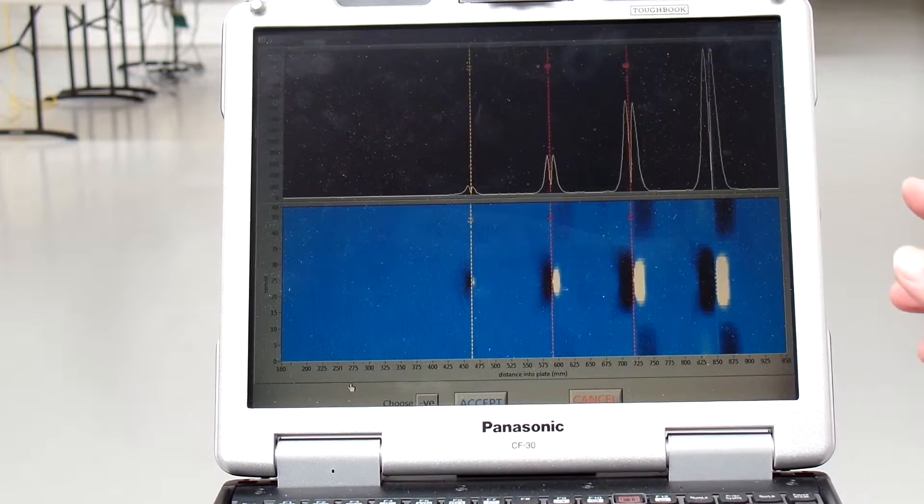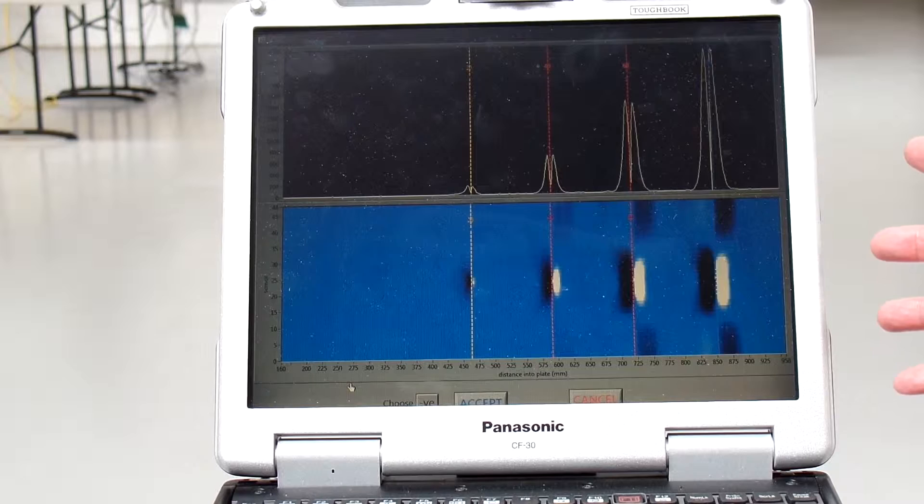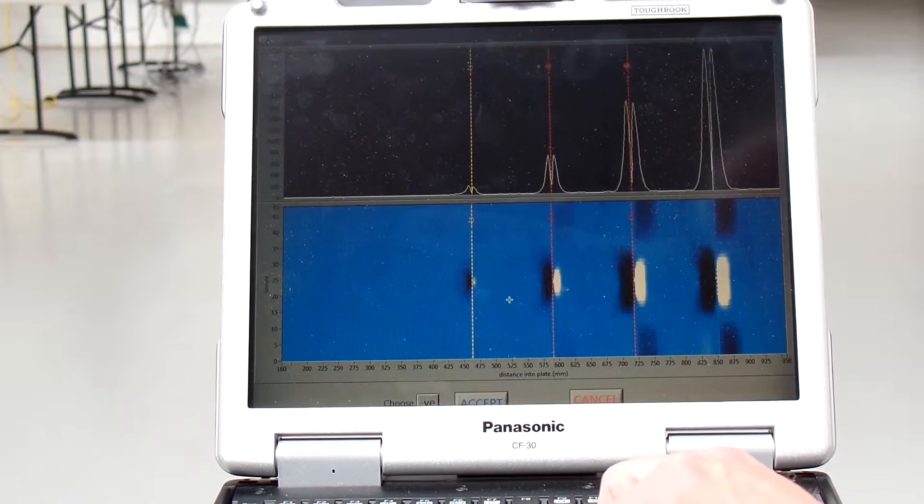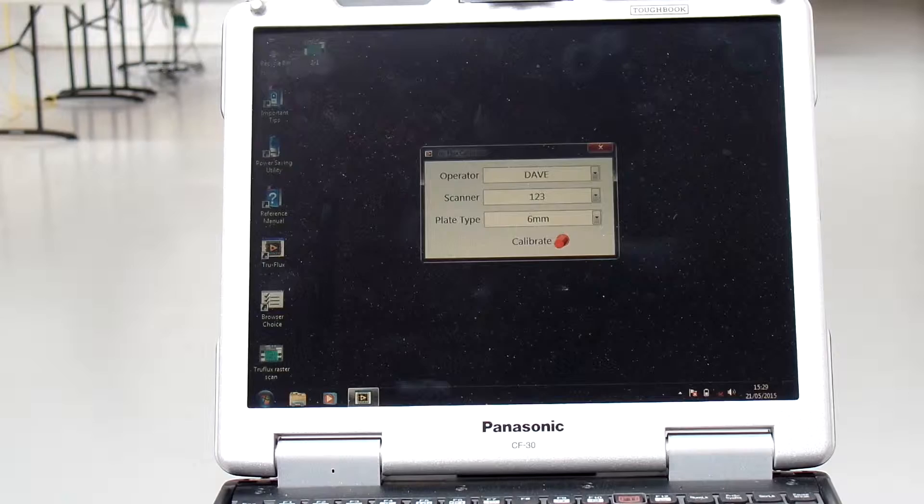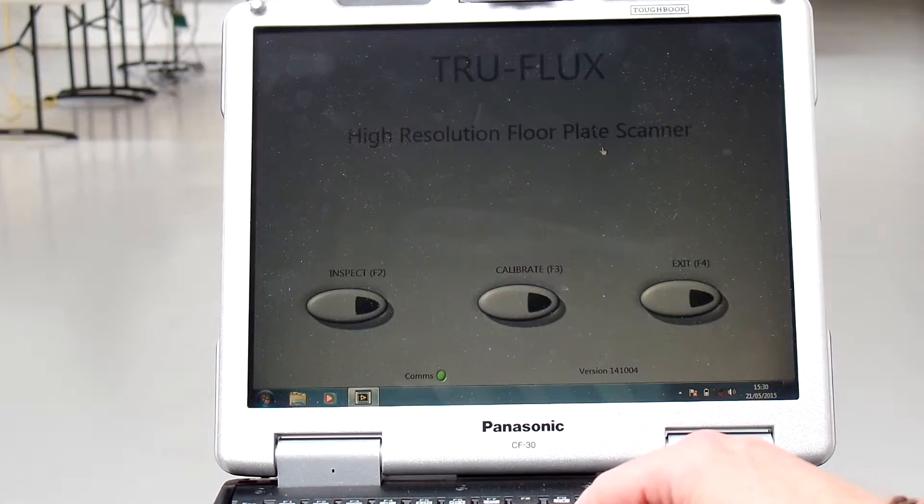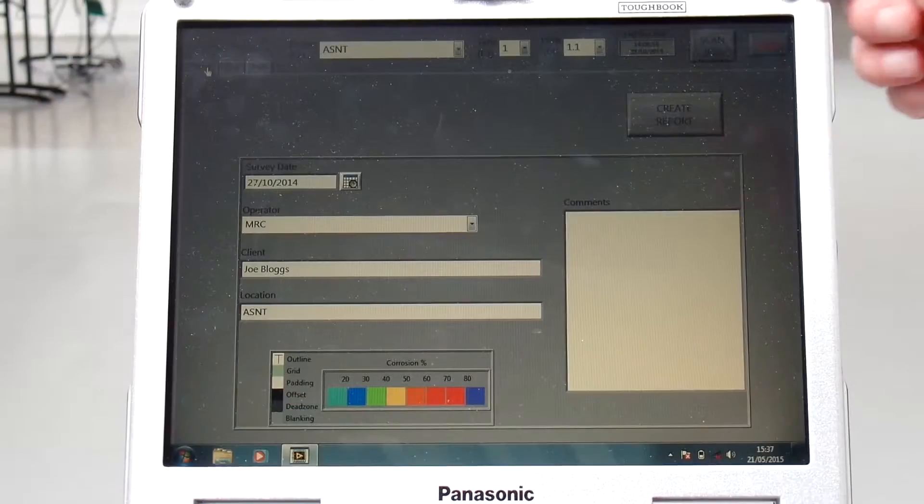With the cursors in place on the indications, we press the accept button to accept the calibration. You must perform a calibration before an inspection. The calibration will be stored for a period of up to 30 days, after which point a calibration must be done again in order to do another inspection. The calibration is now complete. To start an inspection, close the calibration window, which returns you to the main menu where you can select to start an inspection.